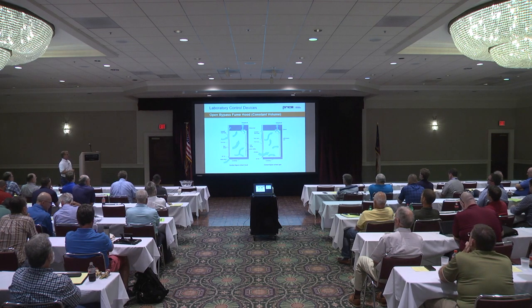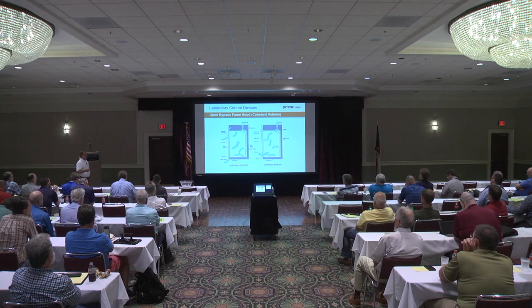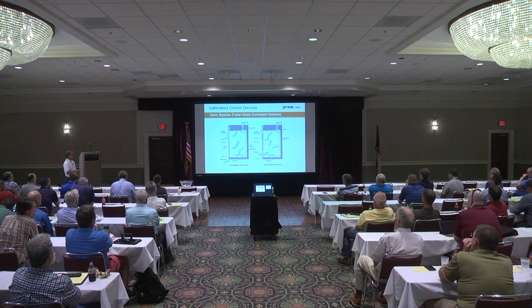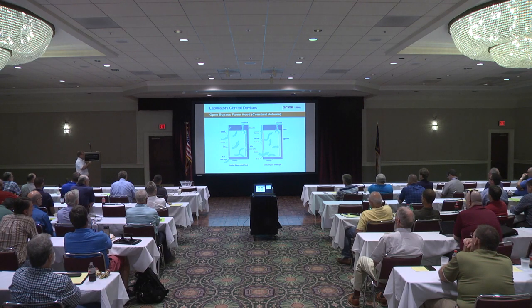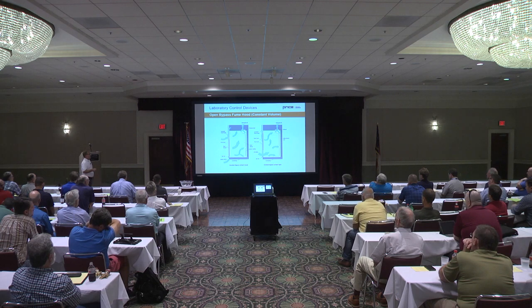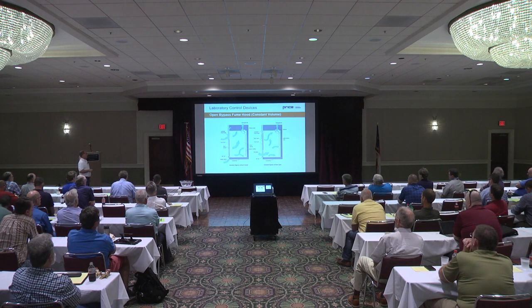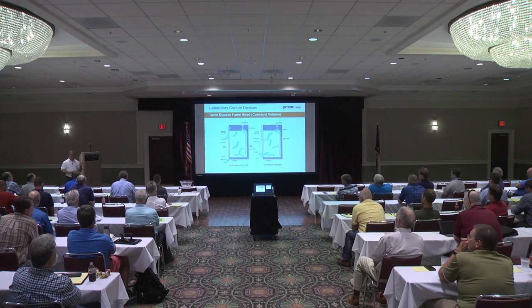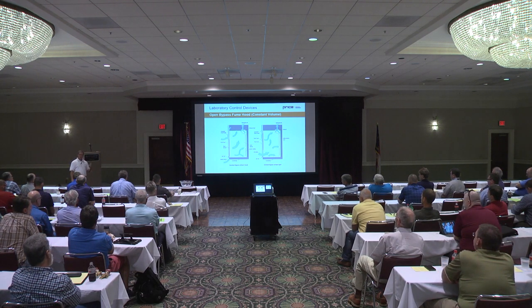So just moving into a little laboratory control devices, such as fume hoods. Probably all seen different fume hood types. You have your louvered front panels, and this is just showing sash closed on the left, how air would go through the hood, sash open on the right, where the sash will come up behind the louvered panel and block most of the airflow through that panel. It's not going to be 100%. Normally see that in a constant volume. Let me back up. We'd prefer to see that only in a constant volume fume hood. Unfortunately, most sites buy fume hoods with louvers for variable volume application.